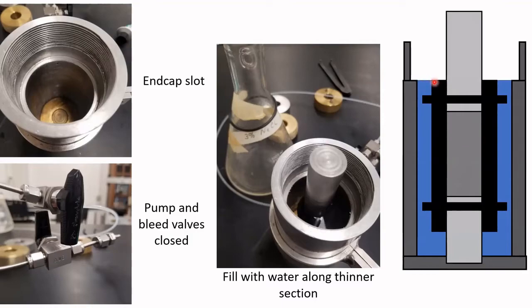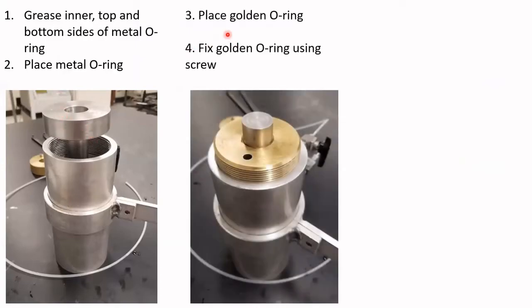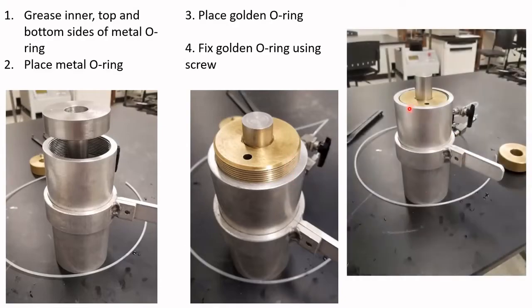Once that is done, we close the vessel. First, we take the metal O-ring and apply vacuum grease on the inner side, top and bottom. Then we place the metal O-ring followed by the golden O-ring. We use the screws at the back to fix the golden O-ring. The result is a closed vessel with both valves closed.